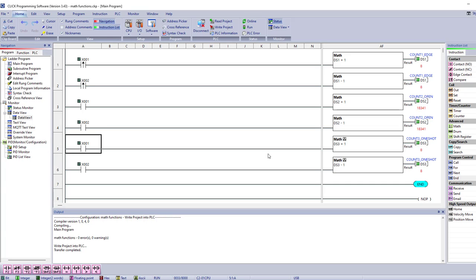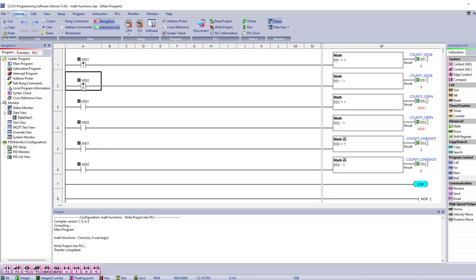You either use an edge-trigger function to do it once, or the one-shot function inside the math to do it once, for every operation. Now if you're going to try and count your scans, that's another story. But we're not doing that. We're counting operations. You want to make sure that you don't double count them.